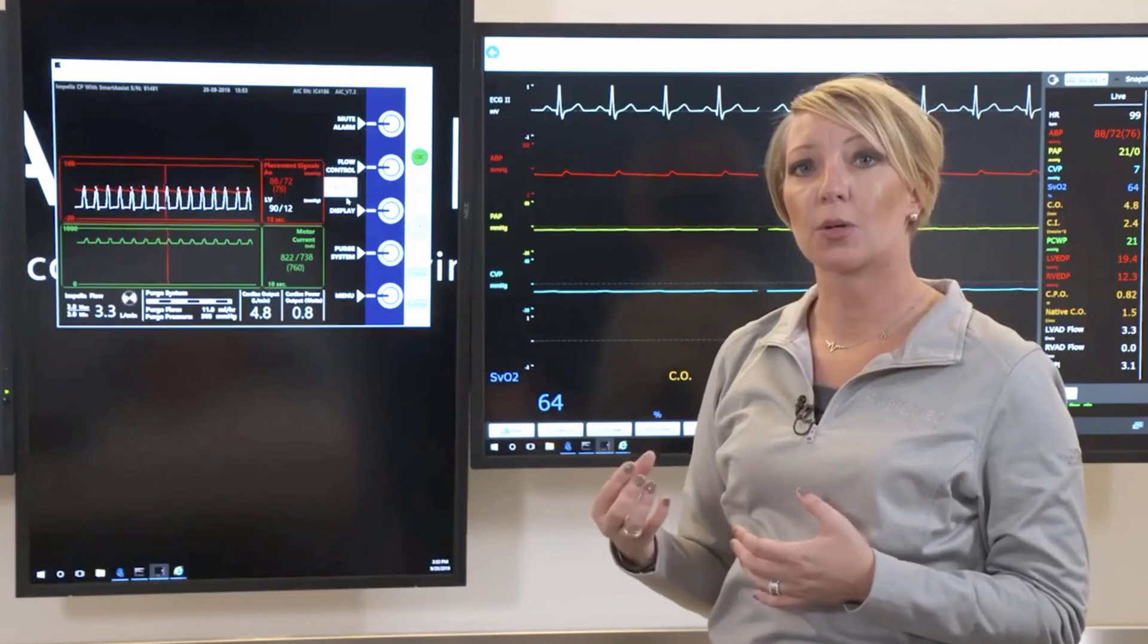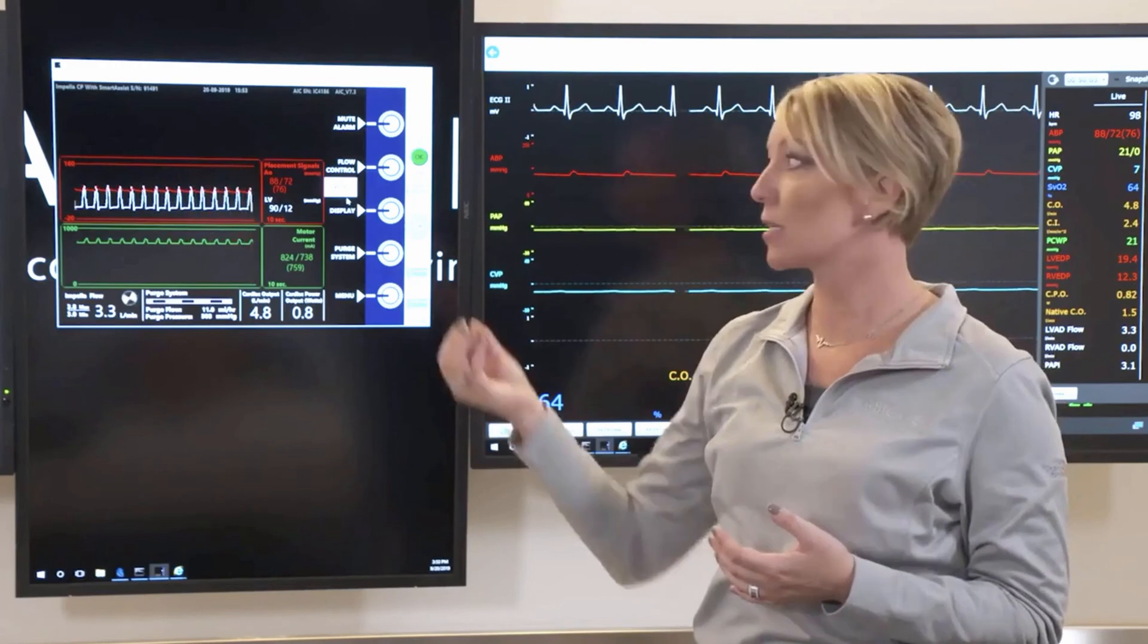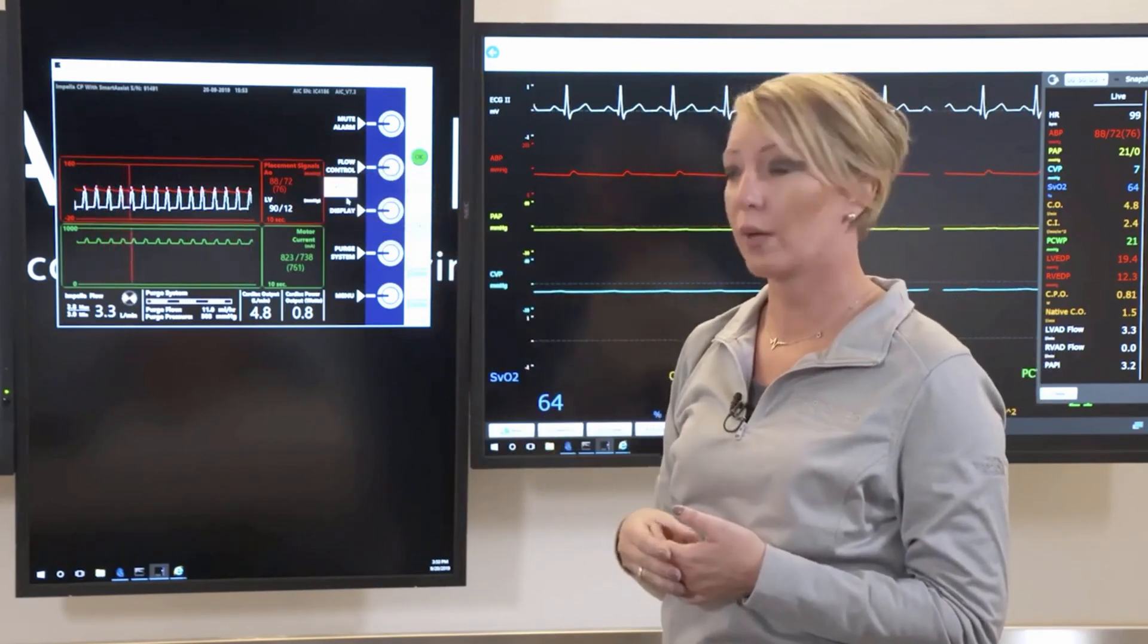The optical sensor is located where the cannula and the outflow meet. So wherever that sensor is, is the waveform that we will get from the red waveform.